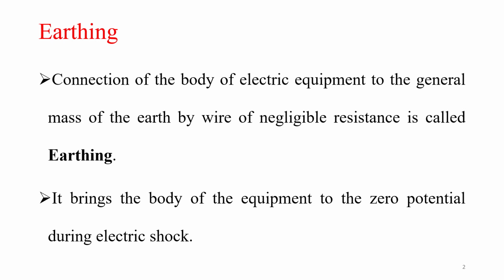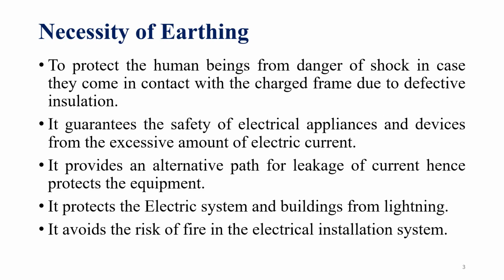Why do we have to make earthing? The necessity of earthing is to protect human beings from the danger of shock. Whenever there is a possibility of leakage current and you are touching the body of the electrical equipment, if the leakage currents are passing through the body of the human being, then he will get a shock. So that leakage current can be passed to the ground through the earthing process. So we will be protected from the electrical shock, and it guarantees the safety of electrical appliances.